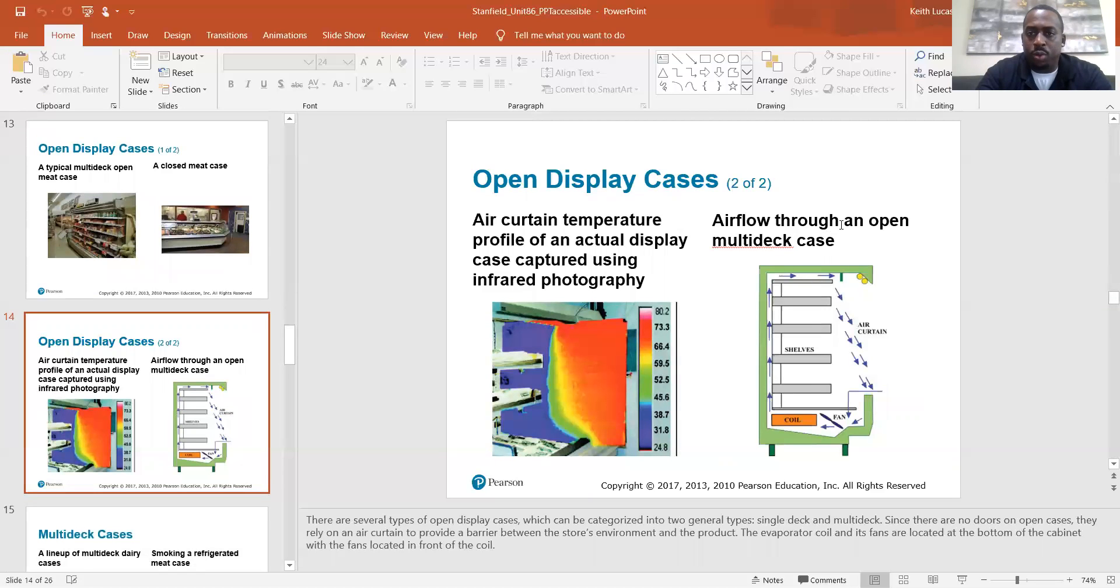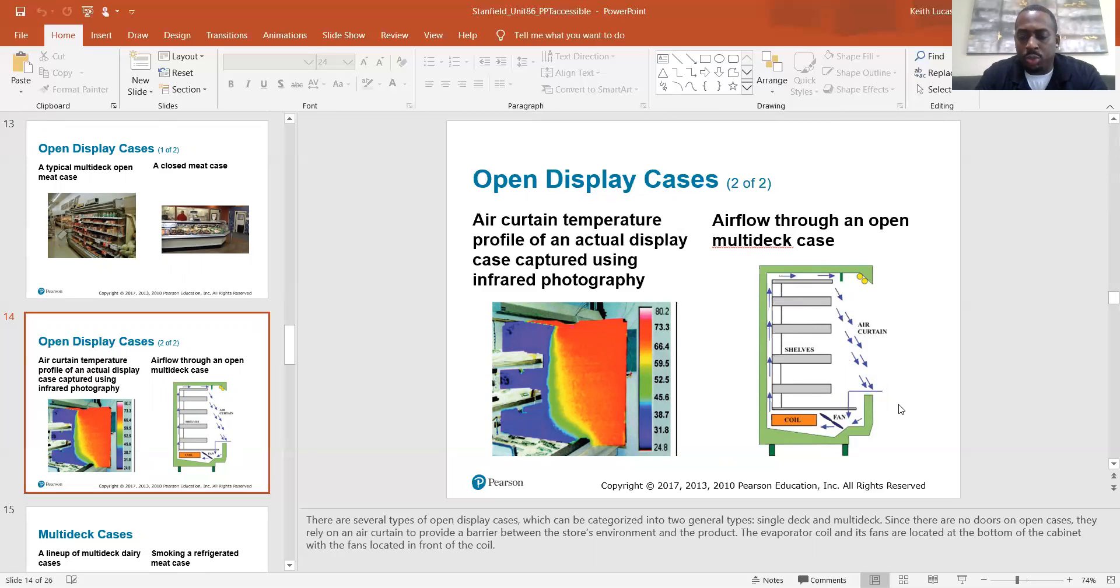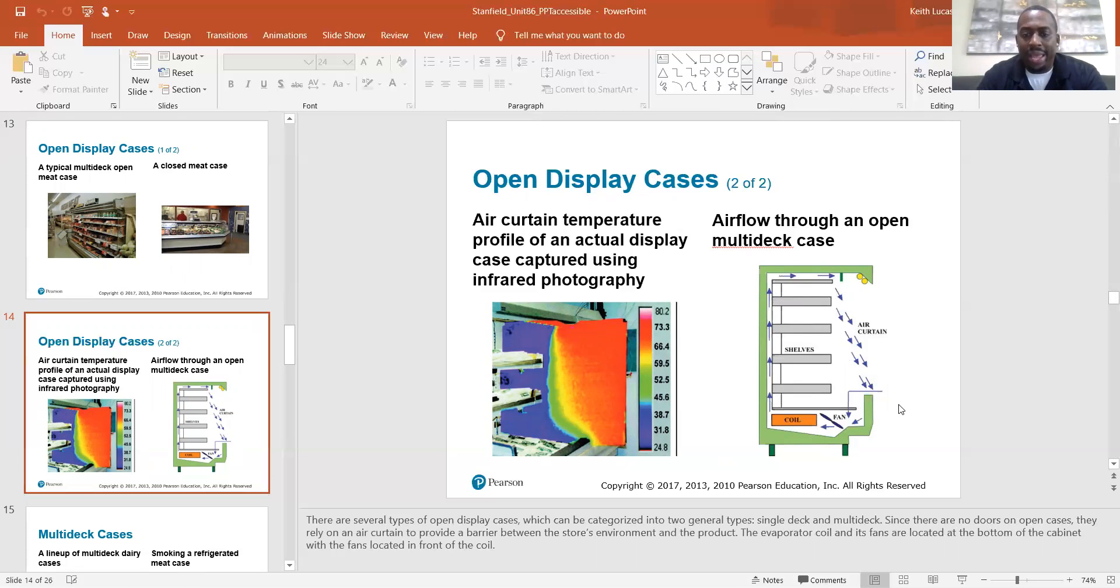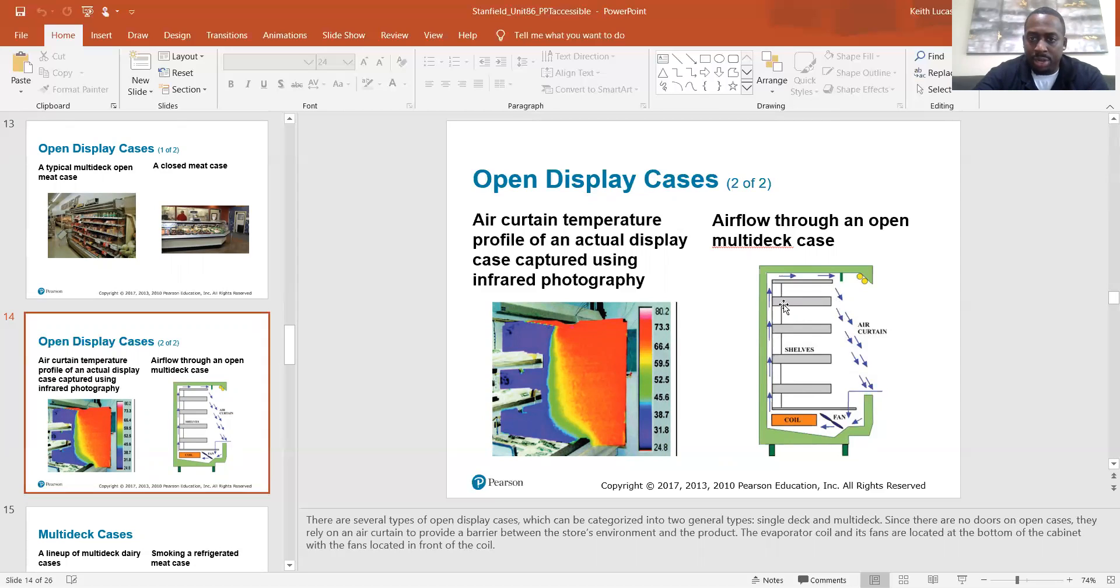And then airflow through an open multi-deck case. So they're showing you your fan is located here, airflow is going around in a cycle. So there are several types of open display cases which can be categorized into two general types, single deck and multi-deck. Since there are no doors on open cases, they rely on an air curtain to provide a barrier between the store's environment and the product. The evaporator coil and its fan are located at the bottom of the cabinet with the fan located in the front of the coil. So you can see here, that's our little fan blade. The fan is blowing this way. So it's sucking the air in and it's blowing it across this coil and it's coming out cold and it's going in this cycle here. It's being directed down.